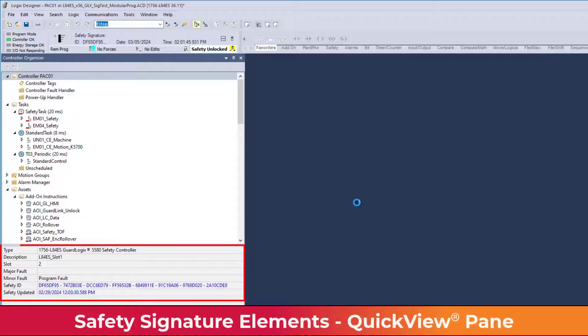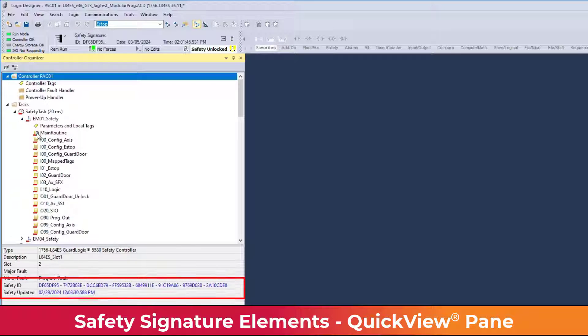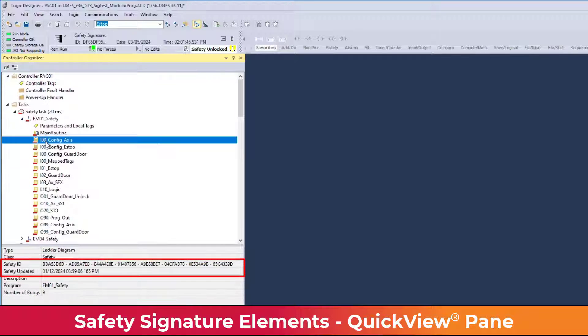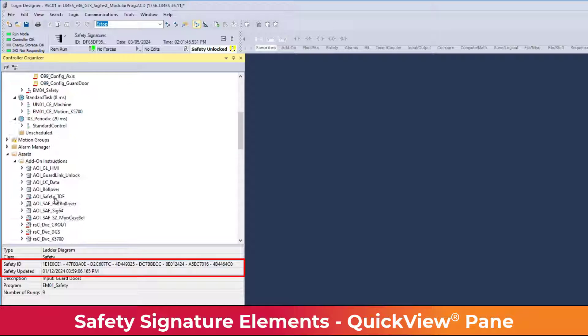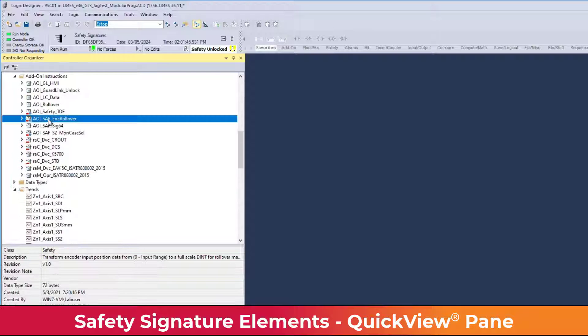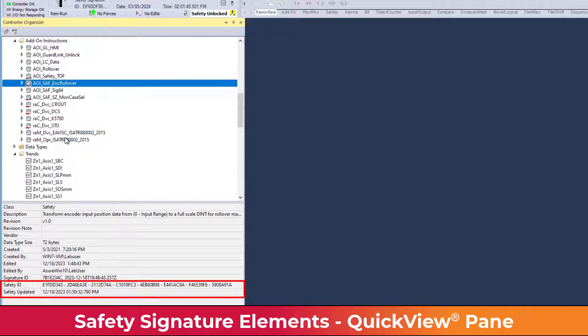The Logix Designer Application Quick View pane displays the safety ID and safety updated time of each signature element. Click on any element in the active organizer to see the element's signature. Sometimes the Quick View pane must be dragged up from the bottom of the screen to show the safety information.